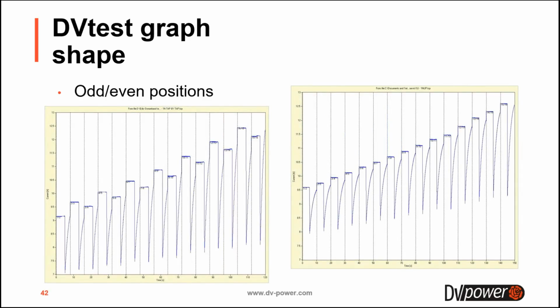Then, especially if it's a diverter switch design, you need to look at the difference between odd and even positions. Here on the left, we have an example of how it looks when every odd or even position has a lower current, which indicates some increased resistance in one of the legs of the diverter switch. On the right side, we have the same graph from the same LTC after the repair. This is linear regulation. Everything should be linear and smooth as it is on the right graph. But on the left graph, if you see any irregularity on every second position, then you probably have a problem in the diverter switch.